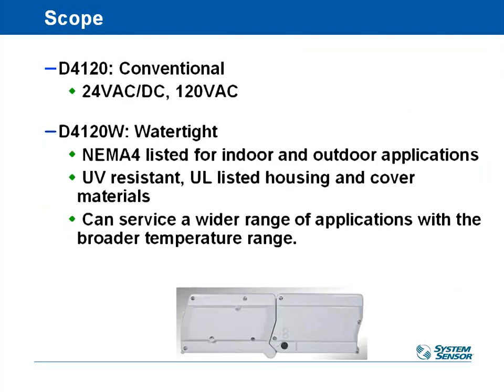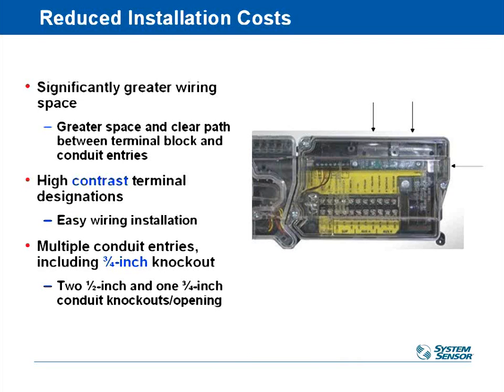You can get 24 volt or 120 volt versions of these detectors. Like I said, there is a watertight version, the D4120W, W for watertight. It can be used indoor or outdoor. Typically outdoor because A, costs more money, and B, it's not clear so you can't see through it like you can on the indoor ones. The plastic is UV resistant, so it can be out in the sunlight, which is obviously important, and it has a wider range of temperature swings allowed than a typical detector.